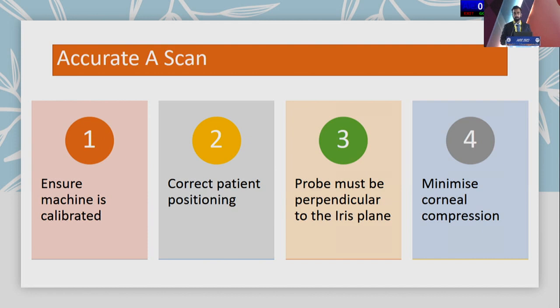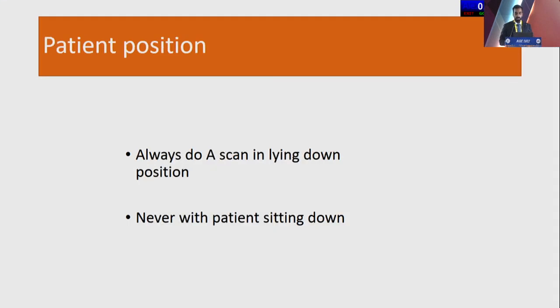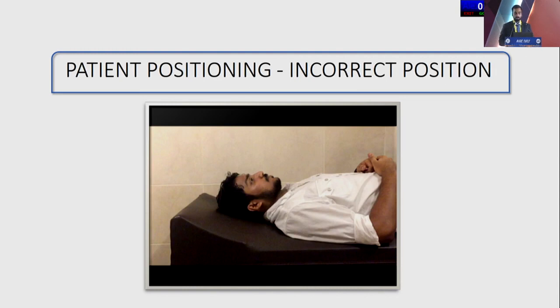So what are the cornerstones of an accurate A-scan measurement? One, the machine should be correctly calibrated. We should ensure that the patient is in the correct position. The probe must be absolutely perpendicular to the iris plane, and there should be minimal corneal compression. It would be ideal to do the A-scan with the patient in the lying down position and never with the patient sitting down. So this is an example of incorrect positioning. As we see here, the patient is lying down with the head at an angle. This is bound to give you errors because the angle of incidence at which you place your A scan can be inappropriate. You will not be going at the anatomical visual axis.